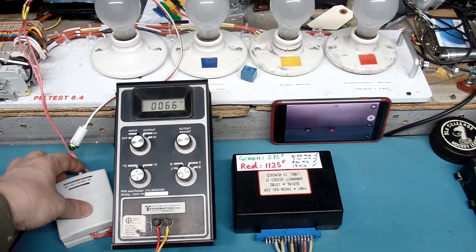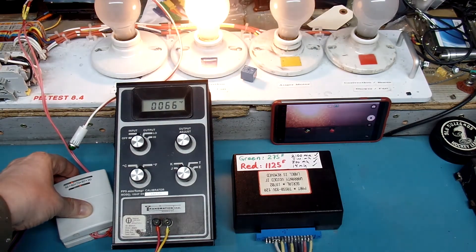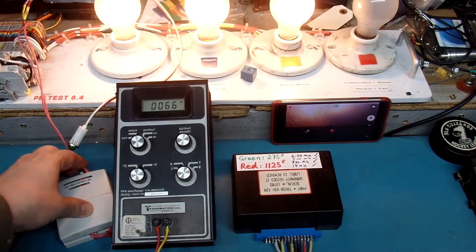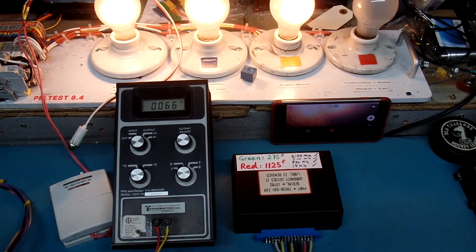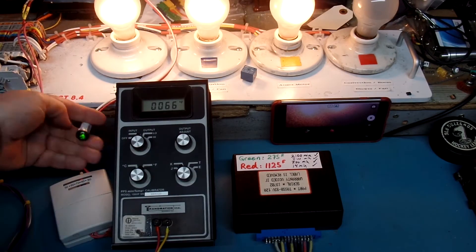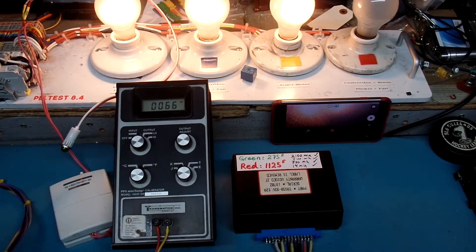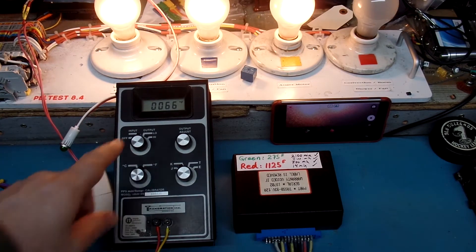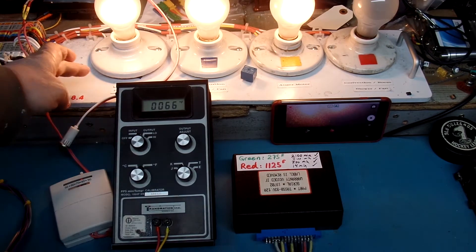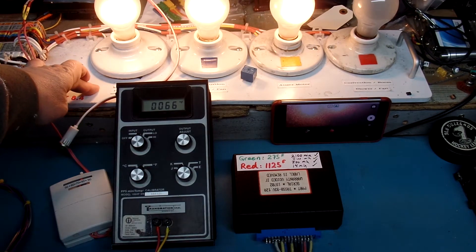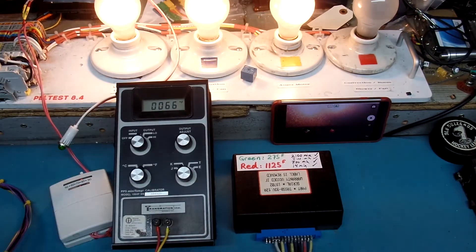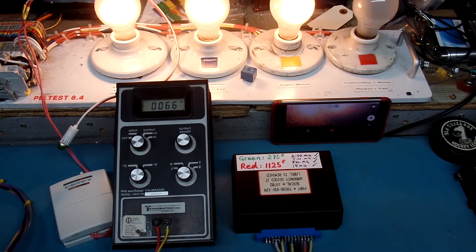Let's go ahead and do another call for heat. I'll turn that off and turn that back on. Thermostat is now calling for heat and we're at 66 degrees Fahrenheit. We see that that called for the igniter to come on, the combustion fan is running, and so is the auger motor dropping pellets into the fire pit.